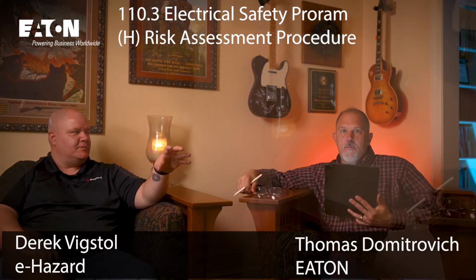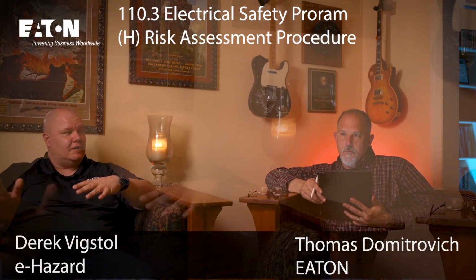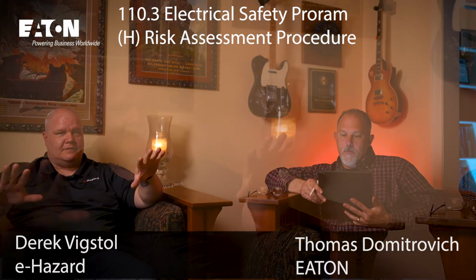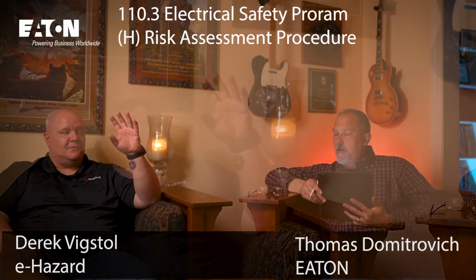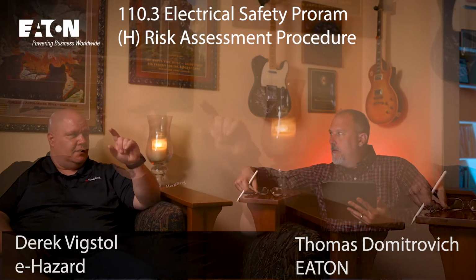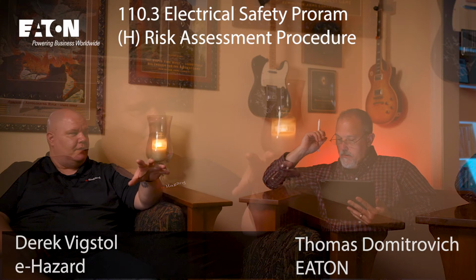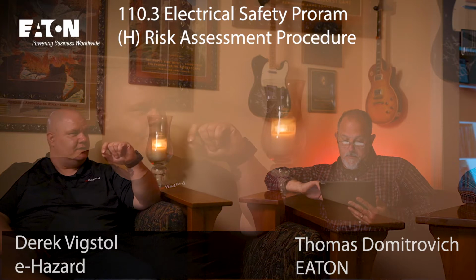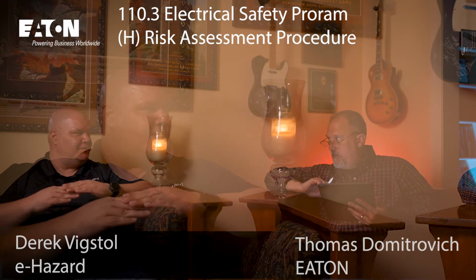So risk assessment, and the way you build this out in your ESP is you got to understand what risk assessment is trying to do. And 70E specifically calls out that risk assessments must be performed for both shock and arc flash. And so they're separate hazards, so we're going to do one for each. It's to identify when a hazard exists in the work we're doing. It's to identify or estimate the likelihood of occurrence of injury from that hazard, and then what's the potential severity from that injury or hazard. And then the result of the risk assessment helps inform us on what we are going to do about this thing.